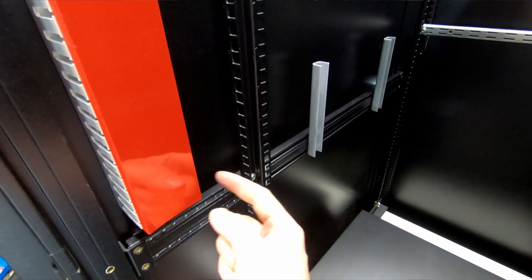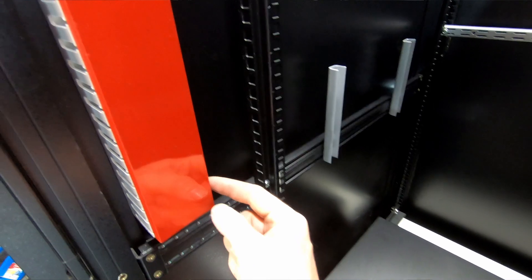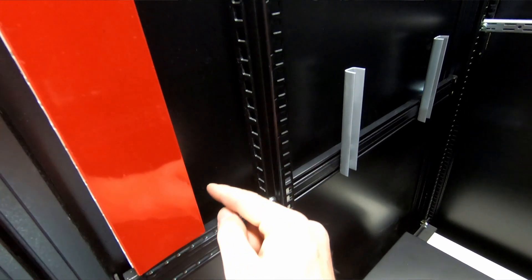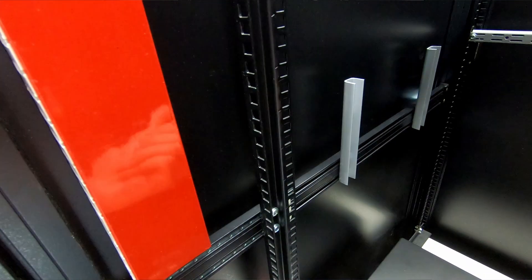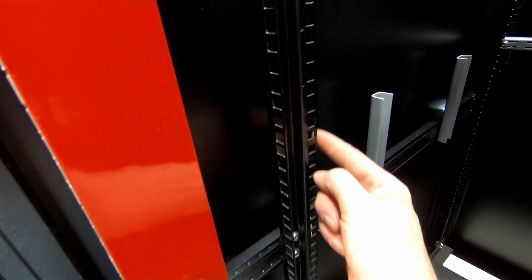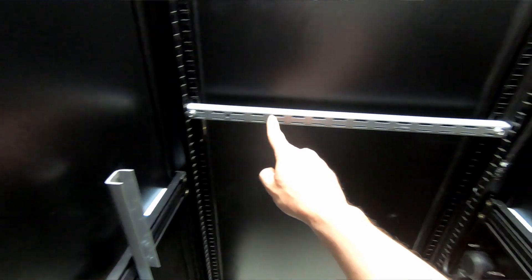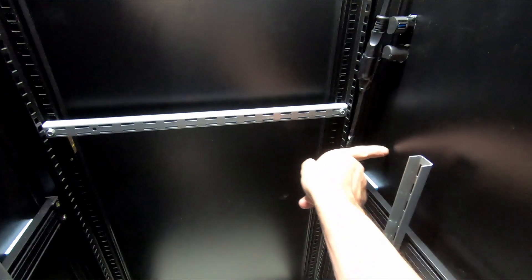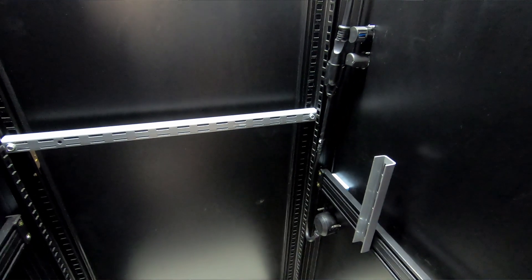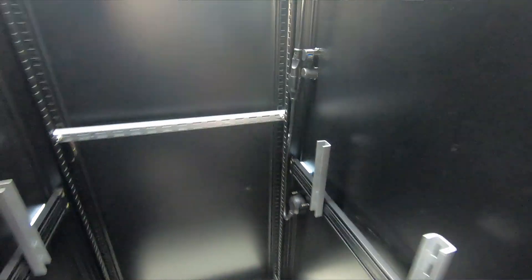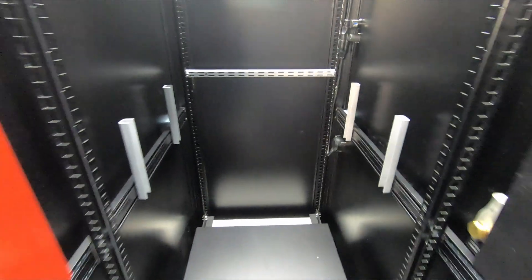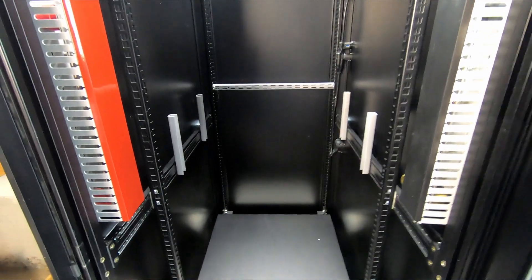connect here, and then turn and run out. And then my positive cable—I have a T-class fuse coming. So I'm going to run the T-class fuse out and then run the lug up like the negative cable and loop it down, connect it here, connect it on the backside here, and then run it across this rail. And then again, out with a gland over here.